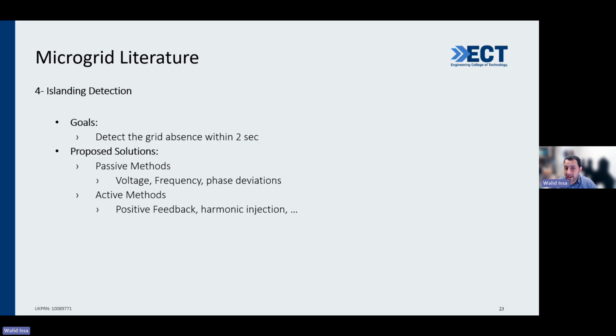And there are passive methods and active methods, a lot of methods in the literature, and one of them is that the inverter keeps perturbing the frequency. Perturbing means perturbing the frequency of the bus. Now, if the grid is present, the grid bus frequency will be 50 hertz all the time. So if the inverter tries to perturb it, it will not move. But if the grid is absent and the inverter tries to perturb the frequency, for example, from 50 hertz to 50.1 hertz, 50.2 hertz, that means the grid is absent. So the perturbation is happening every second. And if the perturbation is successful and the frequency moves, that means the grid is absent and we have to take action.